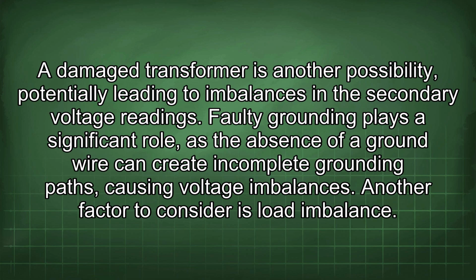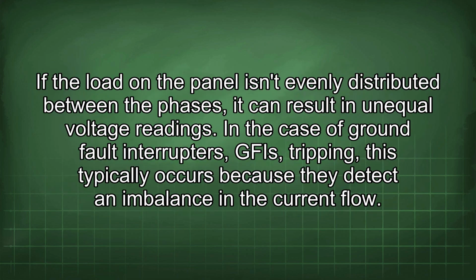Faulty grounding plays a significant role, as the absence of a ground wire can create incomplete grounding paths, causing voltage imbalances. Another factor to consider is load imbalance. If the load on the panel isn't evenly distributed between the phases, it can result in unequal voltage readings.